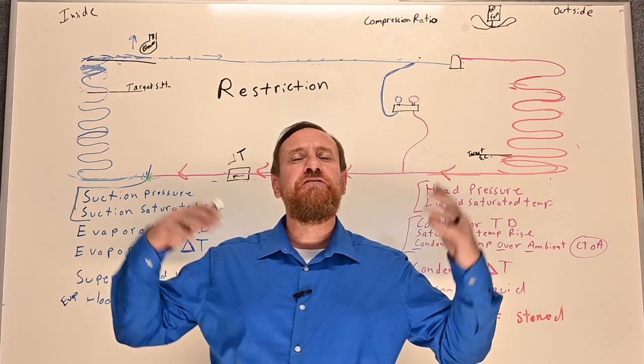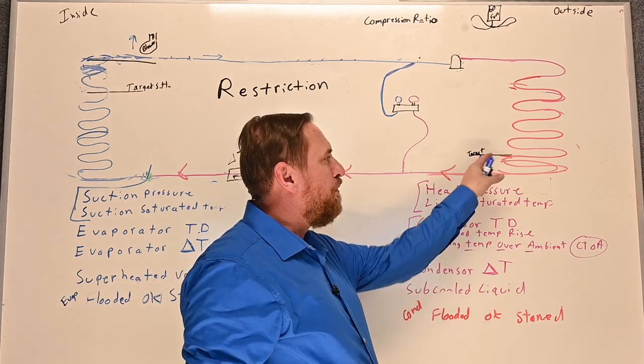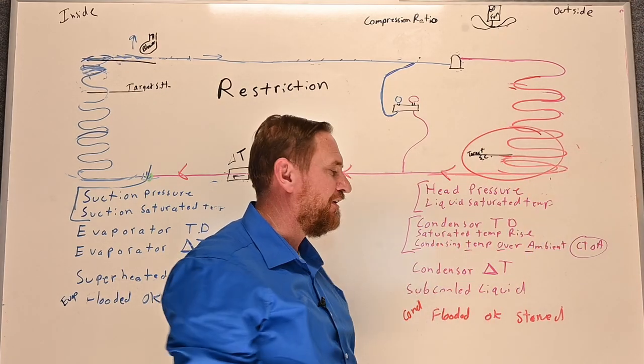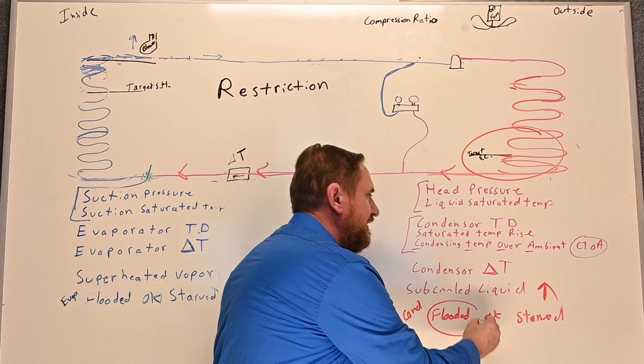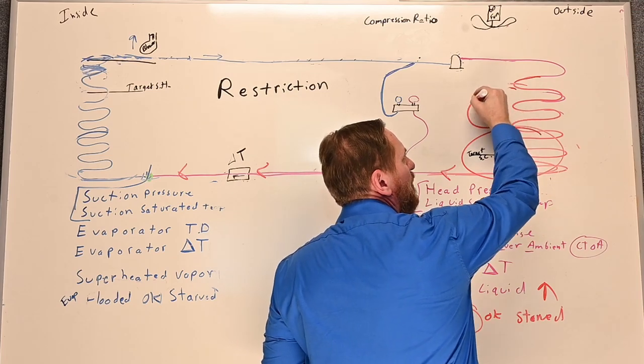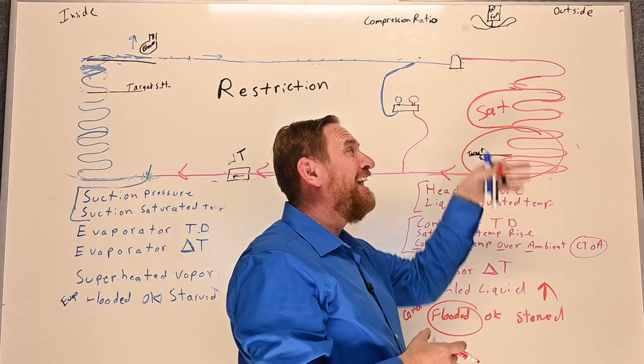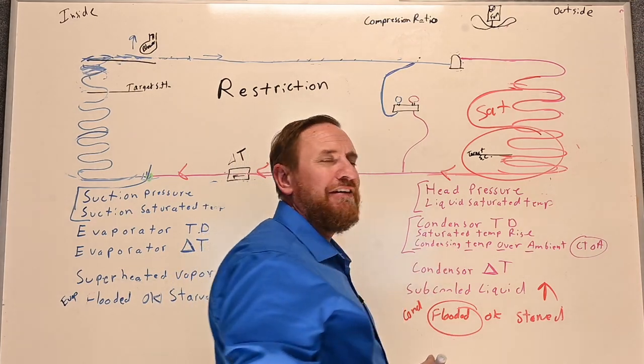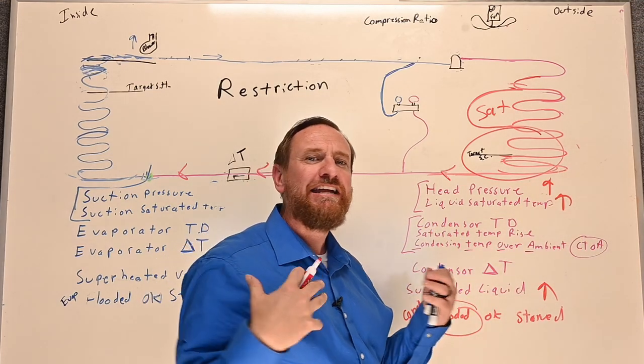Let's see what happens to the refrigeration cycle when we have a restriction. If we have a restriction, the refrigerant flow is limited. We end up with too much subcooled liquid in the condensing unit — our subcooling goes up and we get what's called a flooded condensing coil, because all the refrigerant is backing up inside the condensing unit. Because we have too much subcooled liquid, there's a much smaller area for saturation to occur.